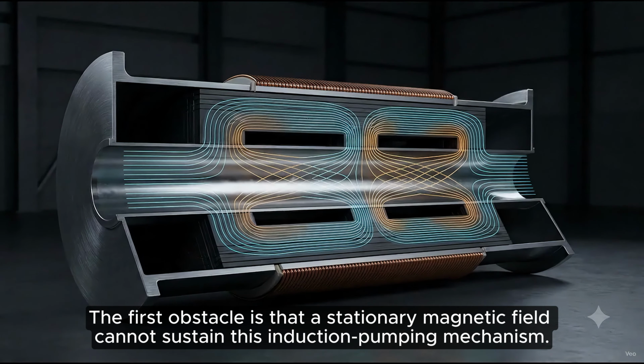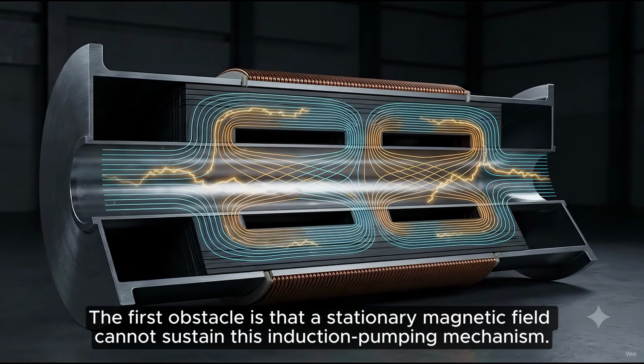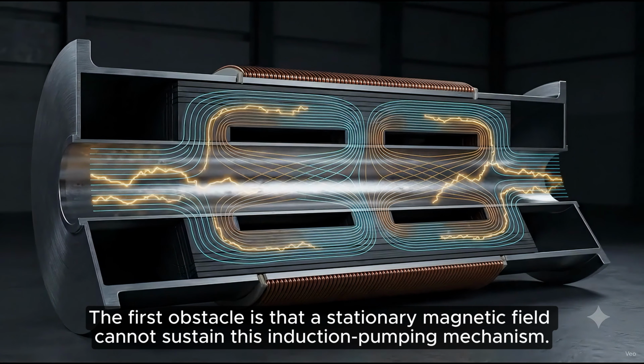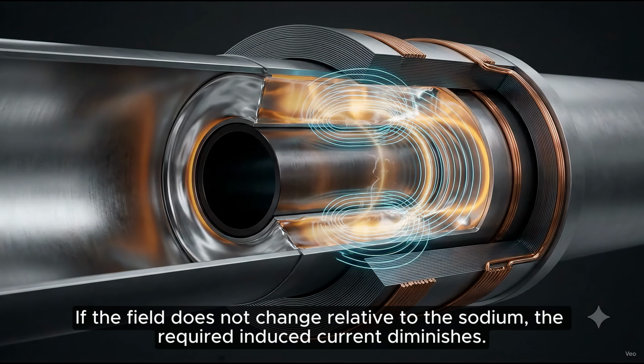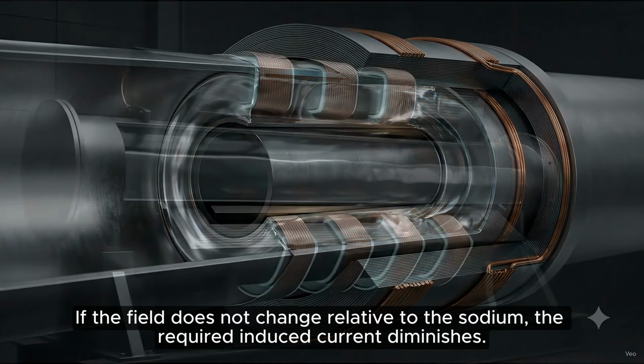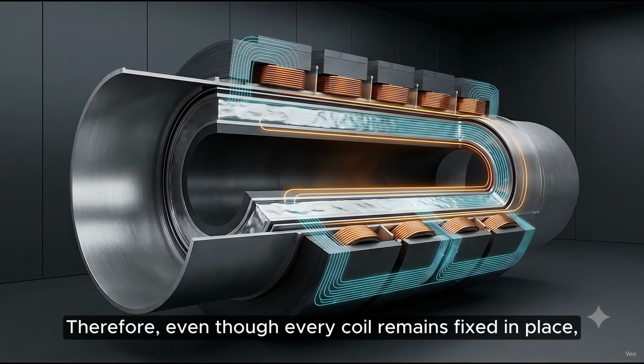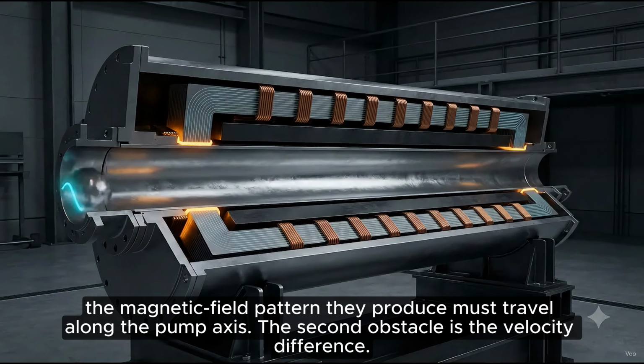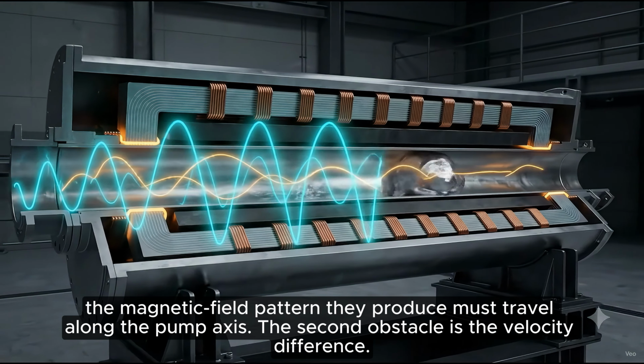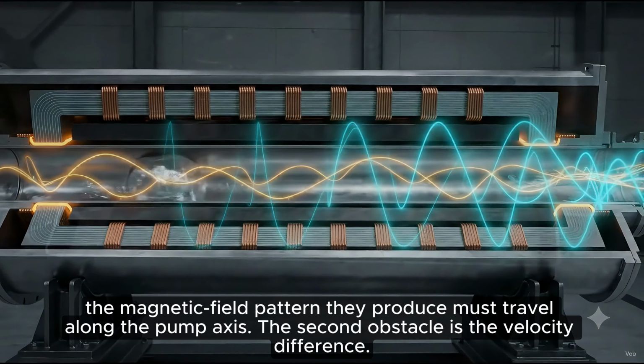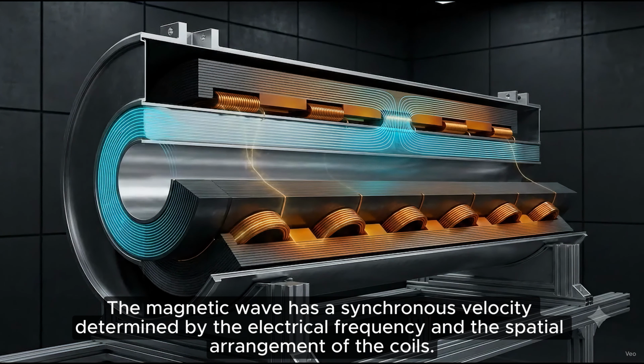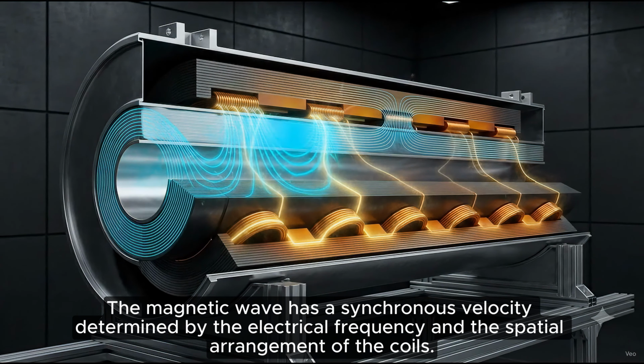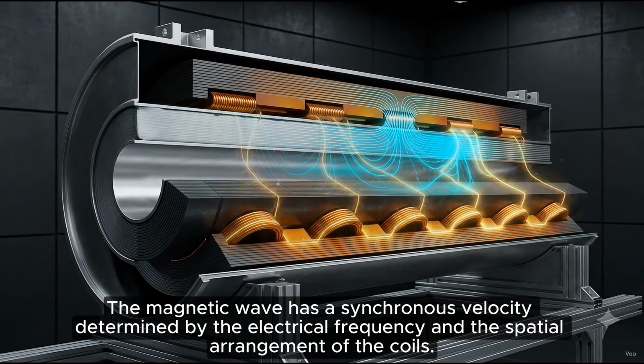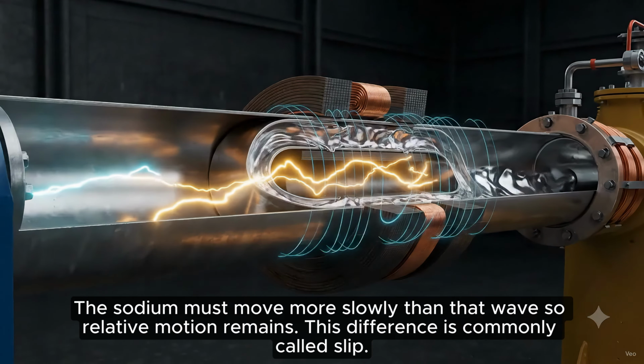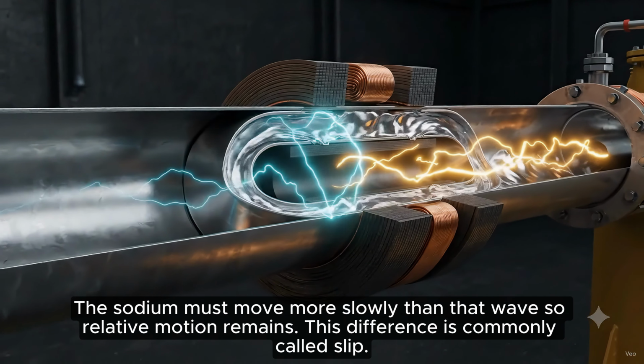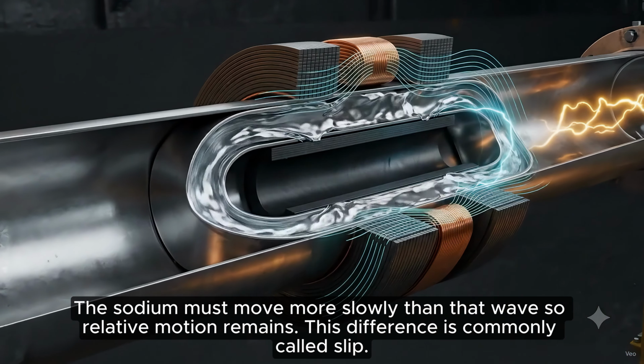The first obstacle is that a stationary magnetic field cannot sustain this induction pumping mechanism. If the field does not change relative to the sodium, the required induced current diminishes. Therefore, even though every coil remains fixed in place, the magnetic field pattern they produce must travel along the pump axis. The second obstacle is the velocity difference. The magnetic wave has a synchronous velocity determined by the electrical frequency and the spatial arrangement of the coils. The sodium must move more slowly than that wave, so relative motion remains. This difference is commonly called slip.